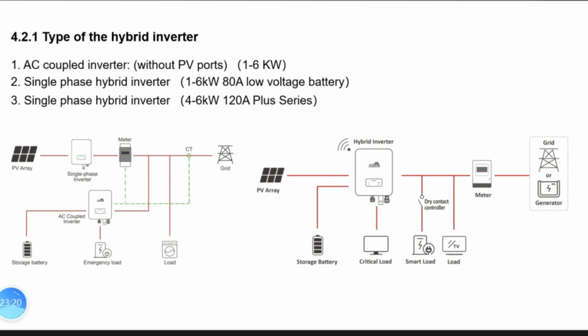And also the AC coupled series from 1 to 6K for the existing PV system. It's very easy to add these storage functions. You don't need to change the configuration of the existing PV panels, and you don't need to change the wiring of the whole system. Just plug and play. So all of our single-phase hybrid inverters work with low voltage battery packs. Here is a picture to show the system wiring of the AC coupled one. It's very easy. Just install the meter or CT on the existing system. No matter whether this existing inverter is of our brand or third party, it can be easily compatible.